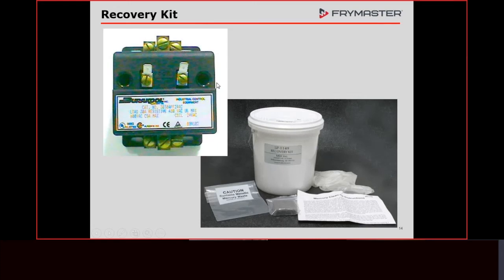You may be working on equipment of ours that has mercury contactors in it. In the time I've been at Frymaster, on 4 or 5 different occasions, mercury contactors that were broken open became a real issue. We had some worse than others. We had one that generated a $10,000 bill. Make sure you have a procedure in place to deal with a mercury contactor that may have broken open and has mercury free in that box.